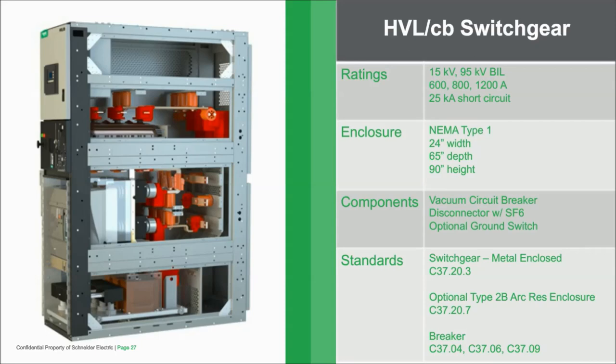Regarding equipment shipping: are the breakers shipped installed in the cabinet or shipped loose? We spent a lot of time on the design team worrying about this. I conducted real-world tests with LTL shipments — having transportation hubs jostle the switchgear to make sure everything was in good shape. For HVLCB, the breaker is installed and shipped fixed in position, not loose, not on a separate pallet. Prem Set is permanently mounted and also ships fixed in position and not separate.